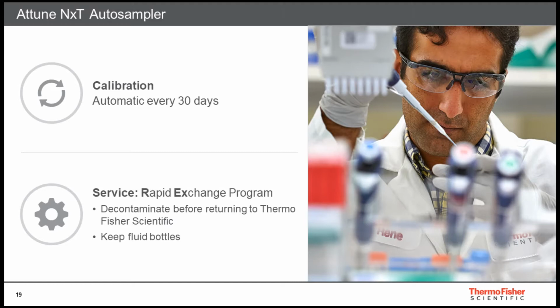The Attune Autosampler is serviced through the Rapid Exchange program, whereupon a new autosampler is shipped for next day delivery once an official complaint is initiated. After decontaminating the defective autosampler, ship it back to Thermo Fisher in the same box that the new autosampler arrived in. Please ship us the defective autosampler within a week. Please use the containers, power, and communication cables from the previous autosampler, as they will not be sent unless specified during the complaint initiation.